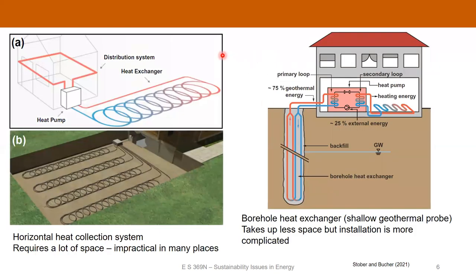Here are how some of these shallow geothermal systems work. There's a horizontal heat collection system — a series of coils buried a meter or two below the surface that act as a heat exchanger. You pump cool working fluid through the heat exchanger, it absorbs heat from the subsurface, comes back through your heat pump, and you transfer that heat to your house's distribution system. This is a simple system but it requires a lot of space — maybe a couple hundred square feet — so it's not feasible in dense urban areas, but works well in rural settings.